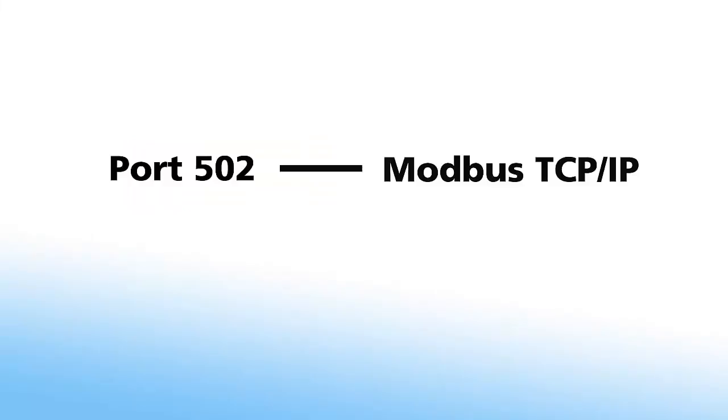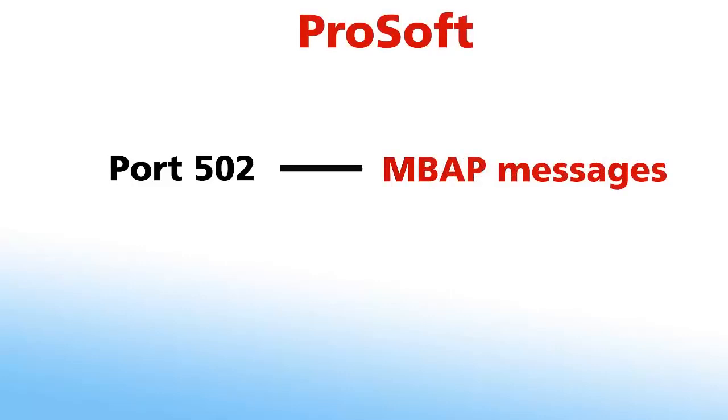Modbus uses port 502 for TCP/IP communication. This is important if your data needs to go through a firewall. ProSoft uses that port for MBAP messaging specifically.